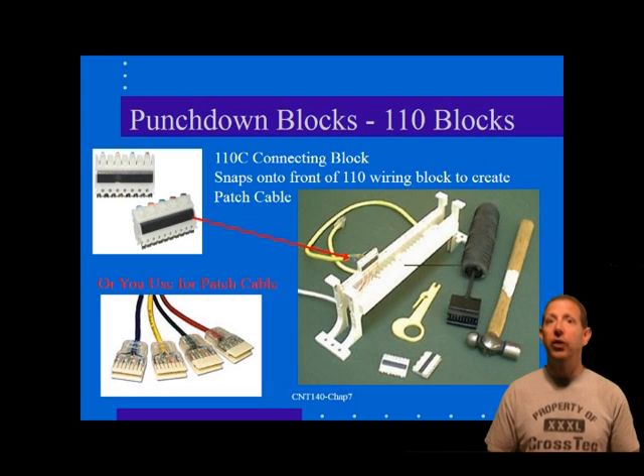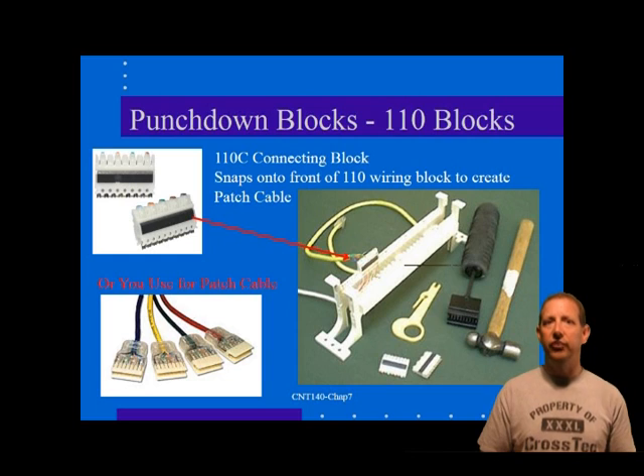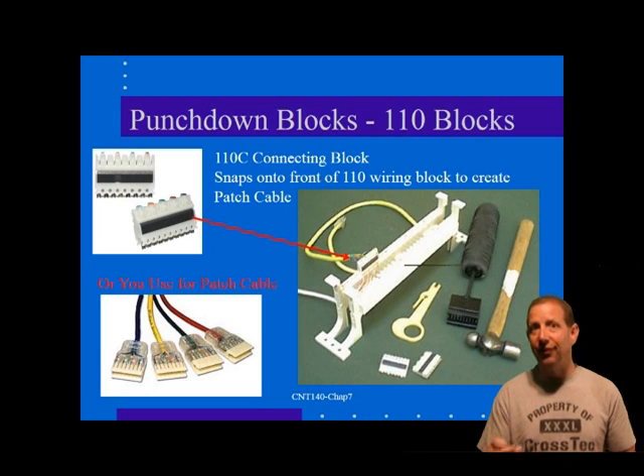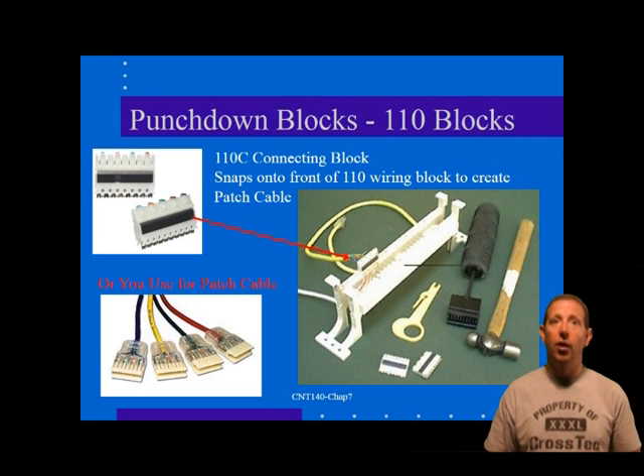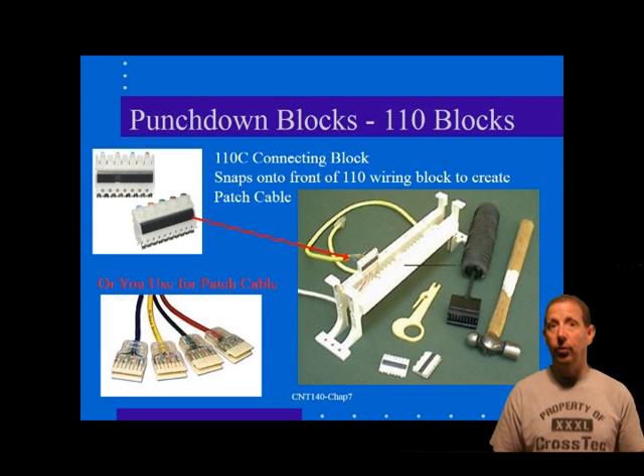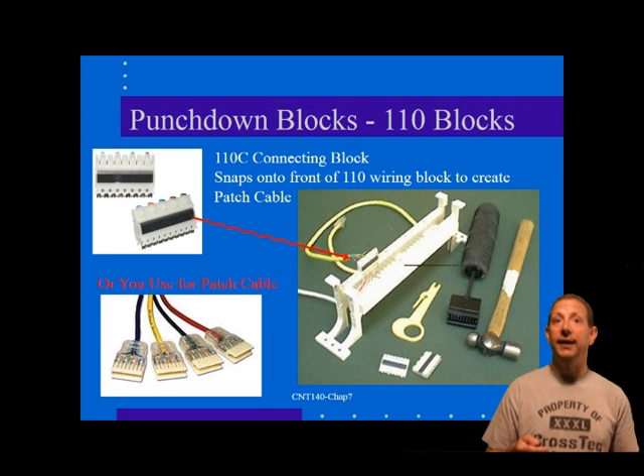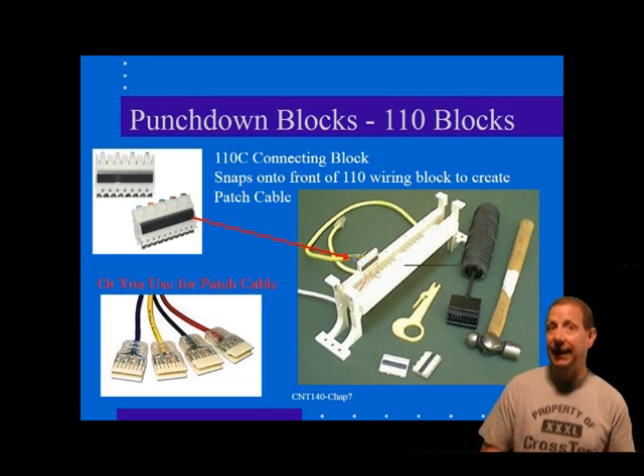The 300 pair wiring block illustrates the potential wiring density of the 110 system and accommodates all 300 pair in a ten and three-quarter inch square footprint. The 110T disconnect block is also available, providing the ability to disconnect the circuit for testing in either direction. Space is available between the index strips to neatly organize incoming cables. In addition, the tip and secondary colors are marked on the strips to help the installer place those wires in the block. The wiring block does not make electrical contact with cable pairs but merely secures them in place.